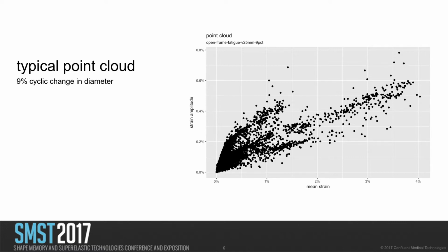We look where that is, and if it exceeds a certain threshold, and use that to determine risk. And that I have always found frustrating because we look at a single point, whether it's above some quasi-arbitrary line, and we decide if a device is good or bad on the basis of that, kind of a binary decision. Not really a great way to assess risk in a quantitative way. Very difficult to create safety factors that are actually meaningful with this approach, but it's kind of the state of the art. It's where we are as an industry.